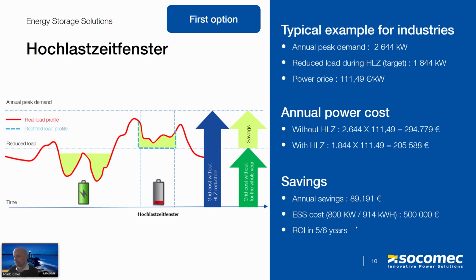So you can see here we have the real load profile. We are charging the battery during the low consumption periods from the grid. Then during this period of Hochlastzeitfenster defined by our grid operator, perhaps between 4 and 5 p.m. in the evening, we are discharging the battery to reduce our peak demand in line with our reduced peak during that period, therefore ultimately being able to benefit from a reduction in cost.